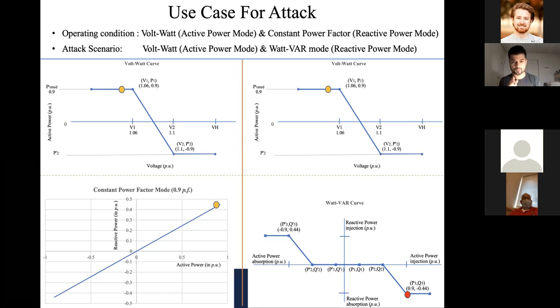Also, one thing to note is that these curve settings can also be changed, and that gives rise to different use cases. You could change one of these volt-watt curves or anything, depending on whether your operator can change these settings. But for now, I'm using all the default values in the standard to keep it simple and focus on this use case, because this use case just talks about the mode change, not the curve settings change. So it's just a mode change, and it's simple that way. So that's the attack, right?